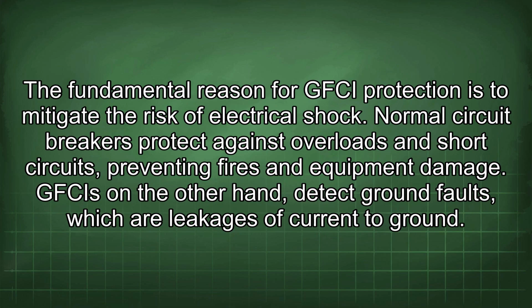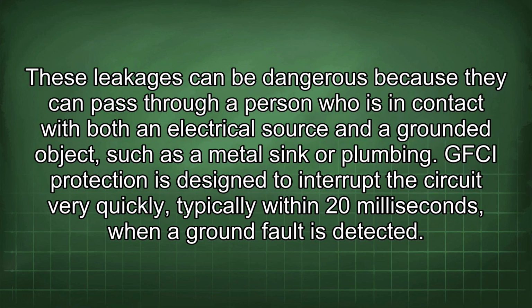The fundamental reason for GFCI protection is to mitigate the risk of electrical shock. Normal circuit breakers protect against overloads and short circuits, preventing fires and equipment damage. GFCIs, on the other hand, detect ground faults, which are leakages of current to ground. These leakages can be dangerous because they can pass through a person who is in contact with both an electrical source and a grounded object, such as a metal sink or plumbing.